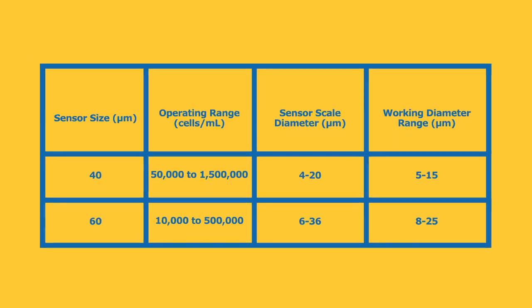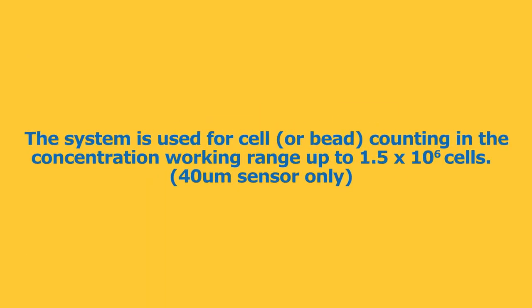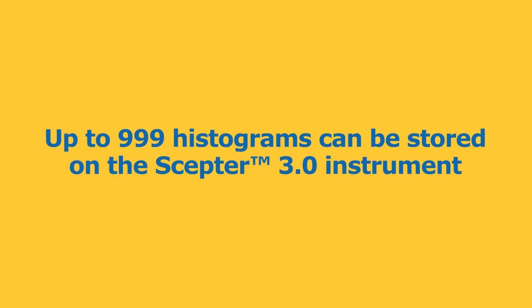The Scepter™ 3.0 instrument and sensors are rated at either 40 and 60 microns. The system is used for cell or bead counting in the working range of 5 to 25 micron diameters and concentration working ranges up to 1.5 times 10 to the 6. Up to 999 histograms can be stored on the Scepter™ 3.0 instrument.